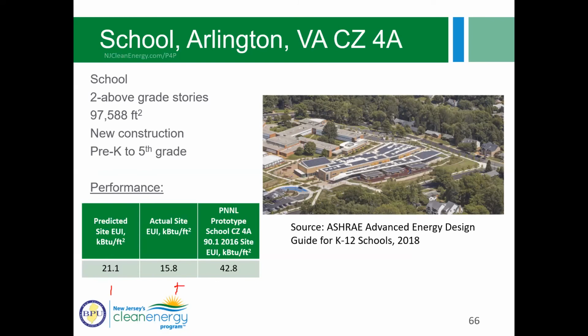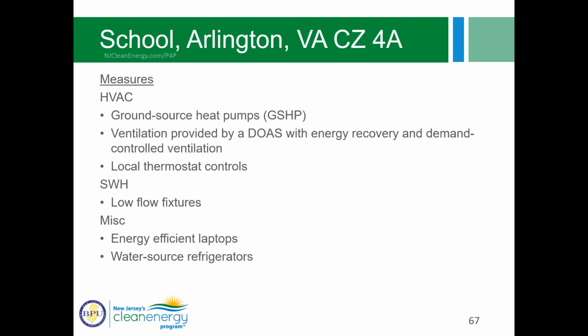And then again, with this reference value, this is the PNNL prototype school, climate zone 4A for vintage 90.1 2016. And that was a 42.8. So really just impressive performance. So what did this design include? Well, it included ground source heat pumps. Once again, ventilation provided by a direct outside air unit with energy recovery and demand controlled ventilation, local thermostatic control, low flow fixtures, energy efficient laptops, water source refrigerators.